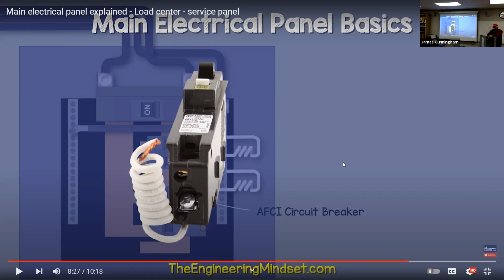If you break out a sub panel off an old panel, and you do it to code, the new sub panel has to have all new circuit breakers, right? You have to upgrade the old breakers you leave behind in the main panel as well. That's a tough question because it usually depends on the inspector. You can try, but I can't tell you that you can get away with it. The code is, if you upgrade your electric, you're meant to upgrade everything to the current code.